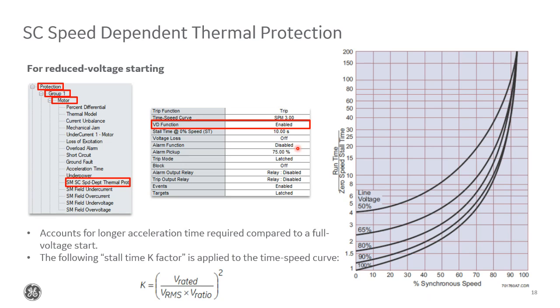The factor that the acceleration torque is reduced is technically the square of the ratio of the reduced voltage to full voltage, and the heating rate is proportional to the square of the starting current. So in other words, since the motor inrush current is reduced proportionally to the voltage reduction, we've come up with this K factor calculation that basically derates the time speed curves based on the level of voltage reduction, and it increases the allowable runtime until overload at any given speed. So on the right here, you can see the standard SPM overload curves shifted upwards.